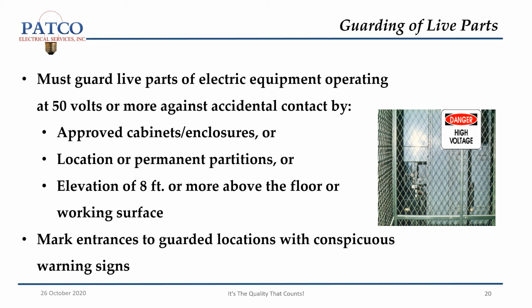Guarding of live parts. You must guard live parts of electric equipment operating at 50 volts or more against accidental contact by approved cabinets or enclosures, or by location or permanent partitions, or by elevation of 8 feet or more above the floor or working surface. Mark entrances to guarded locations with conspicuous warning signs.